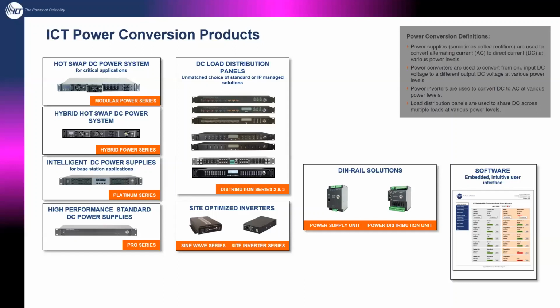We released last year a hybrid version of this, the same configurable, hot swappable, redundant system, but with a built-in converter. So you can have two voltages at site. Primarily you're working with 48 volt equipment, but you've got a couple of oddball pieces that are 12 or 24 volt. You don't need a standalone converter that needs to be rack mounted and wired in line. We've got that built in right there for you in the system.